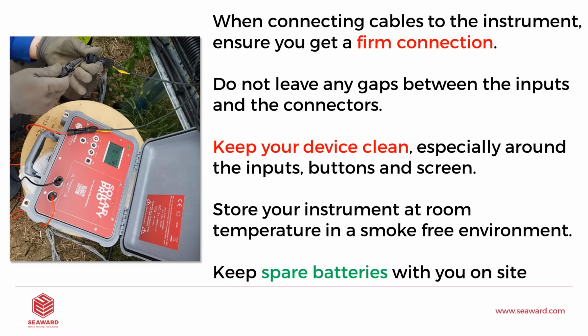So when you're connecting the cables to the instrument, make sure that we make a really firm connection. Okay, we don't want any gaps in those connections because gaps mean arcs. Okay, we should also keep the device very clean. If we get dust and dirt in there, particularly on this site in the Middle East, which I've discussed, this is going to make the buttons stick. It's going to get underneath the screen. It could potentially cause arcs inside of the unit. So we really need to keep it clean and keep the lid shut when we're not using it.